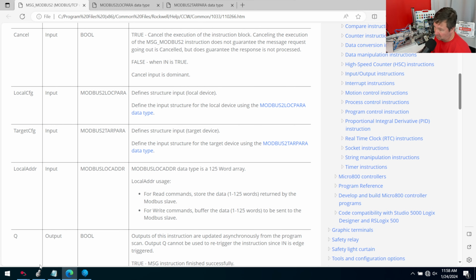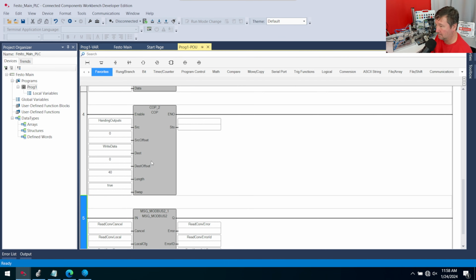So they actually, okay, and here's where sometimes you find out Modbus may be the easier way on this. If I need to add or subtract a 1, that may be the most difficult part. But all right, now that we're reading, writing will be a lot easier. Always try to read data first, because reading kind of tells you that you have your path right and all that type of stuff. When it goes to write, there could be other permission issues, things like that. But all right, let's go ahead and go back offline.